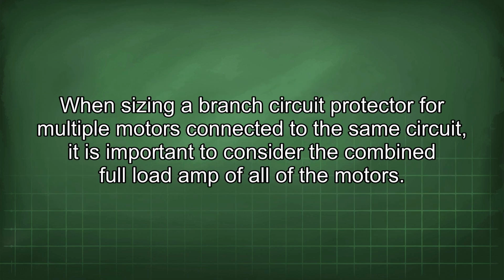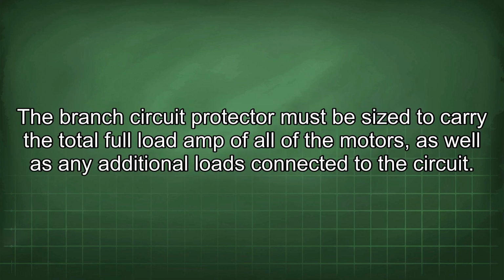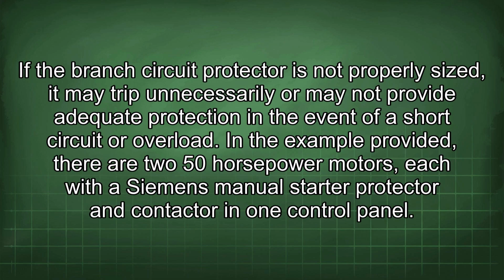When sizing a branch circuit protector for multiple motors connected to the same circuit, it is important to consider the combined full load amp of all of the motors. The branch circuit protector must be sized to carry the total full load amp of all of the motors, as well as any additional loads connected to the circuit. If the branch circuit protector is not properly sized, it may trip unnecessarily or may not provide adequate protection in the event of a short circuit or overload.